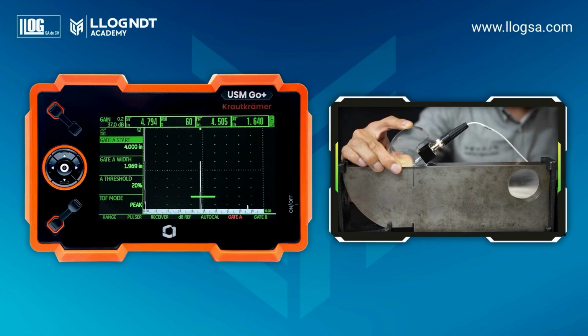Once obtained, without moving the transducer, check if the mark on the wedge coincides with the mark of the 4-inch radius curvature engraved on the block. If it does not coincide, place a piece of tape on the side of the wedge and mark on the tape the point that aligns with the center of the block's curvature. That will be the new index point of the wedge.